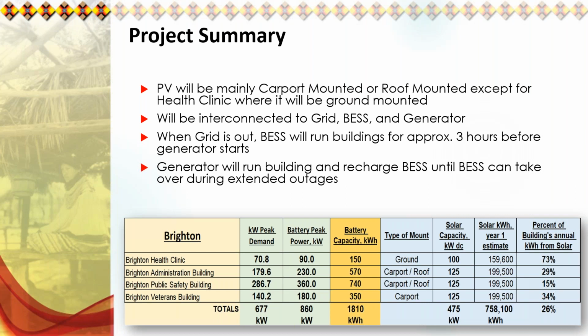The table again shows the amount of energy at each facility we are looking to generate and the battery capacity. As you can see, approximately 26% of the average energy needs of the buildings will be met from these facilities. However, in Brighton, the PV will be mainly carport mounted or roof mounted, except for the health clinic, where it will be ground mounted. It will be interconnected to the grid, BESS, and generator. Again, when the grid is out, BESS will run the buildings for approximately 3 hours before the generator starts. Then the generator will run the building and recharge the BESS until it can take over during extended outages. Next slide, please.